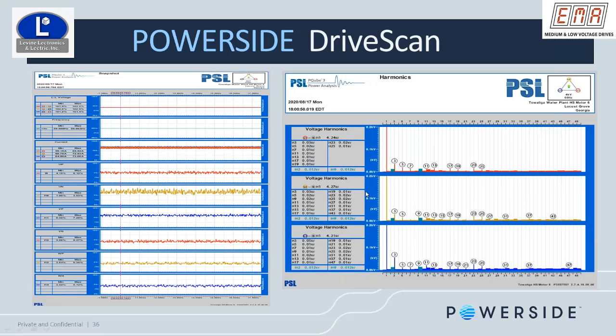This is trending my line voltage, line to line, my current, my frequency, harmonics here. And when I drill into more, I can actually look at the raw data. This is giving me my raw data, 4.245 kV, L1 to L2, and so forth. And I can look at my current as well.